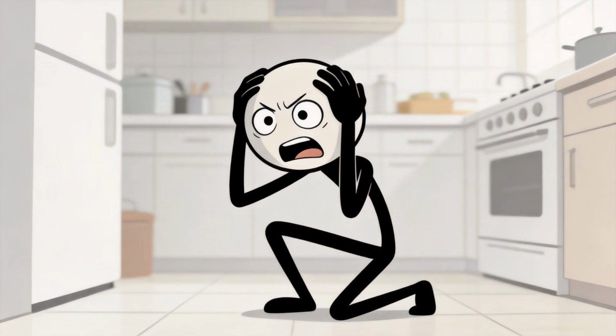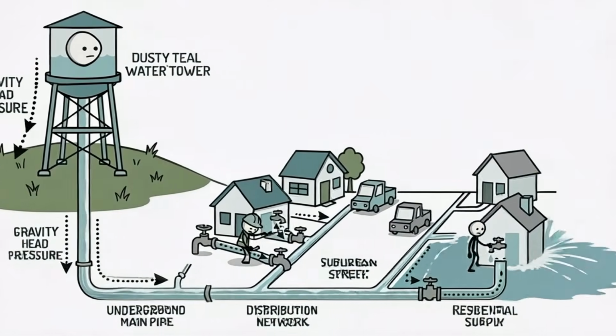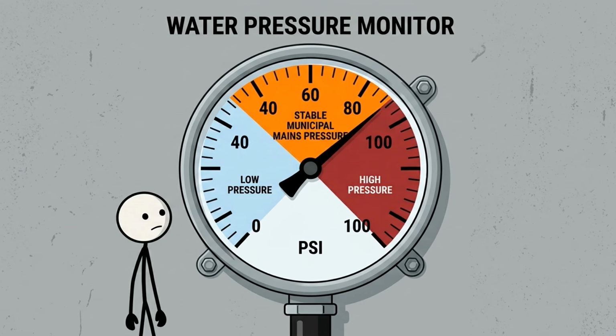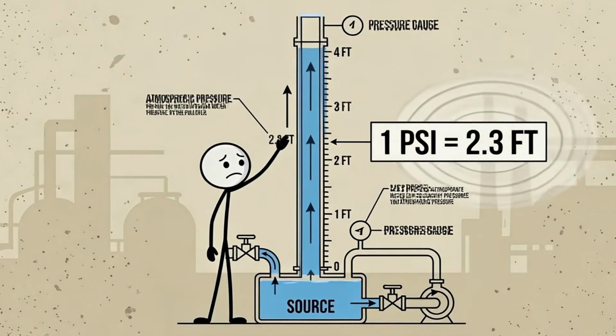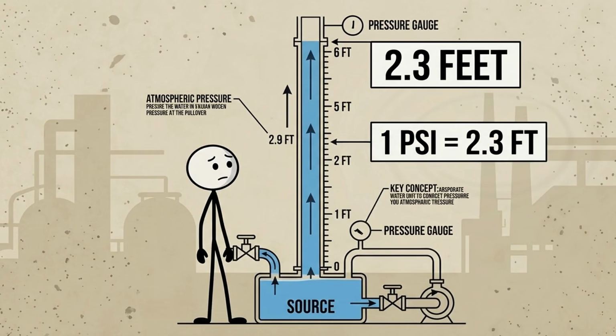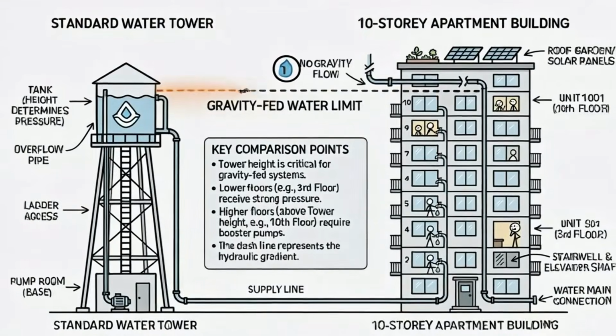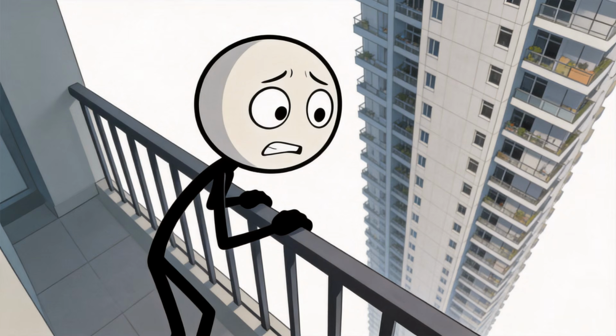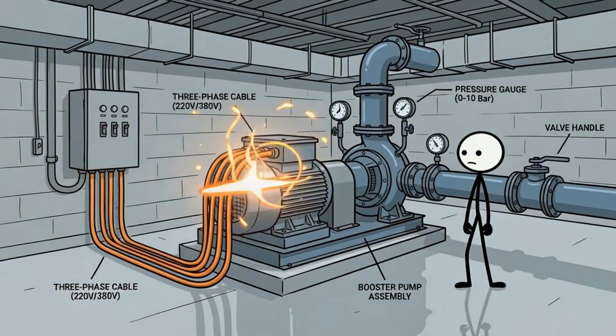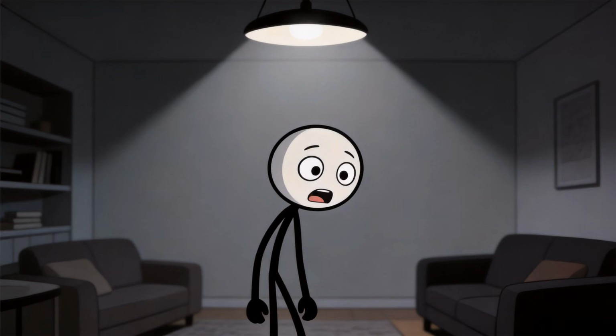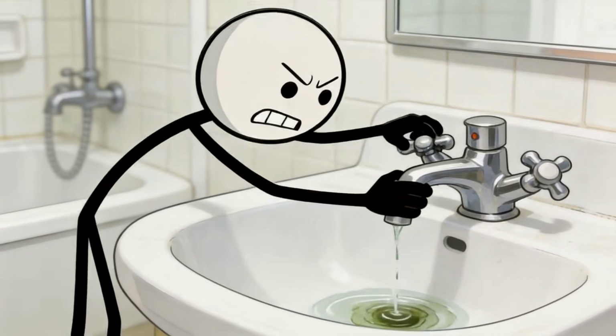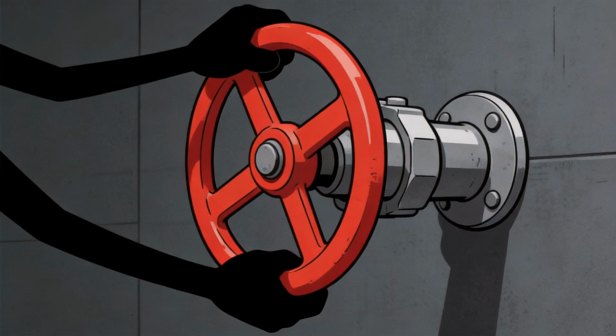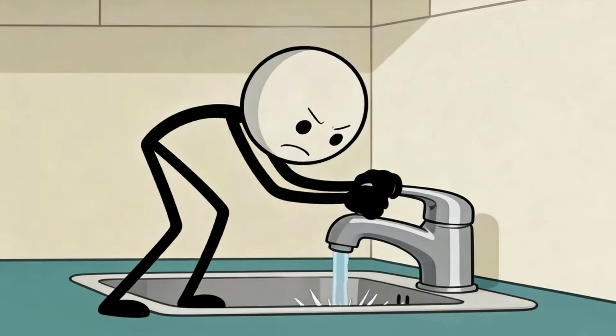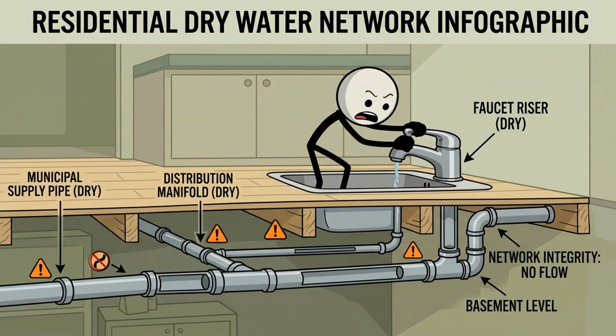At T-0, the localized booster pumps in your high-rise fail instantly. Municipal water networks rely on gravity head pressure from water towers, which provides about 40 to 80 pounds per square inch in the mains. Mathematically, 1 psi lifts water about 2.3 feet. A standard tower can lift water maybe 10 stories up. If you live any higher than that, your building relies on heavy electric booster pumps that require 3-phase power. The second the grid trips, those pumps go dead. Upper floors lose all water pressure at exactly T plus 1 second. You turn on your faucet and nothing comes out. That sudden silence in the pipes is the sound of system inertia dying.